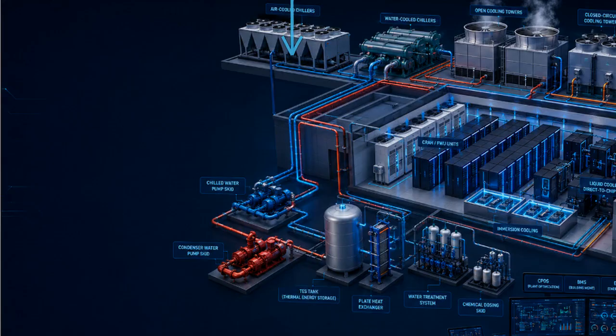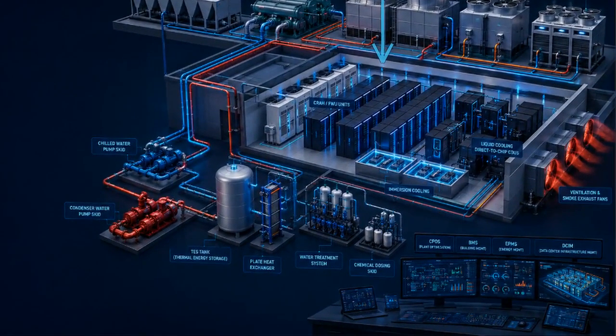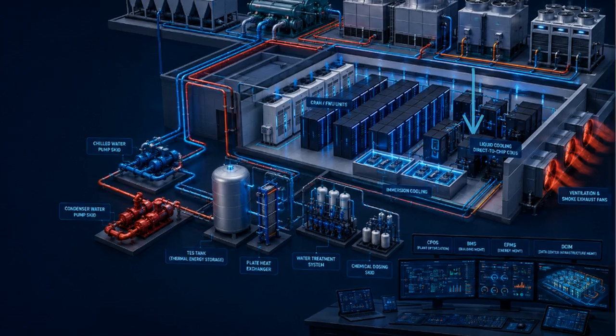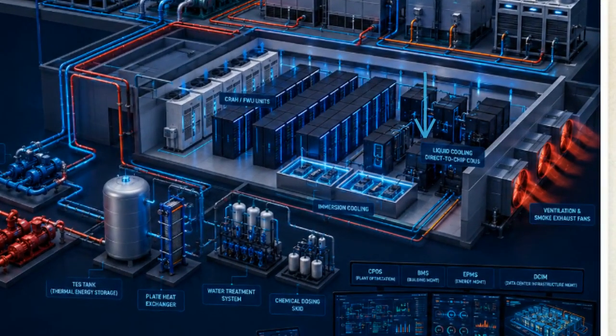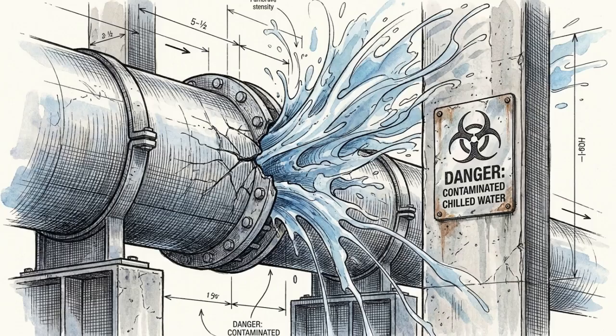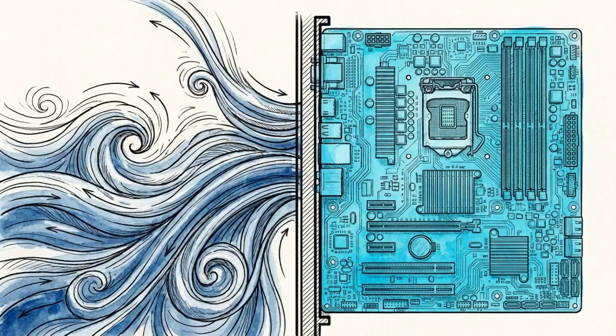This schematic outlines three isolated loops: the blue and red facility water system, the cyan and orange technology cooling system, and residual air. Routing liquid directly to the racks extracts 80% of heat at the silicon, leaving 20% for room air handlers. Pumping legacy single-loop chilled water directly onto the server floor is impossible at this density. You have to establish absolute physical isolation between the raw, high-pressure facility water and the delicate silicon processing cores.